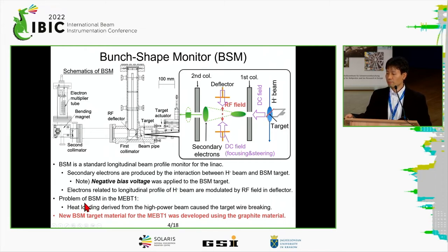The problem of the BSM in MEBT1 is heat loading. This heat loading, driven from the high power beam in MEBT1, causes the target wire to break frequently during beam commissioning.